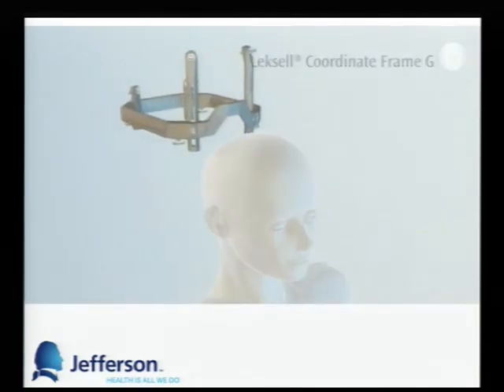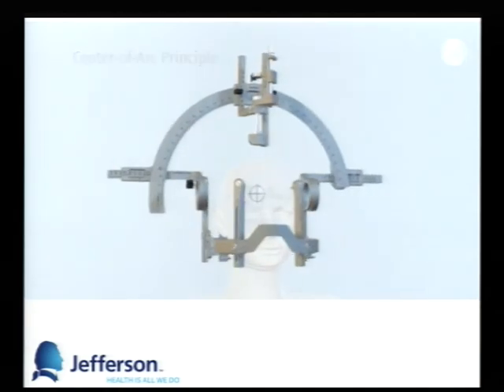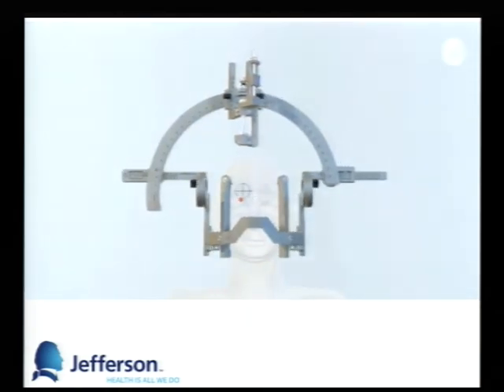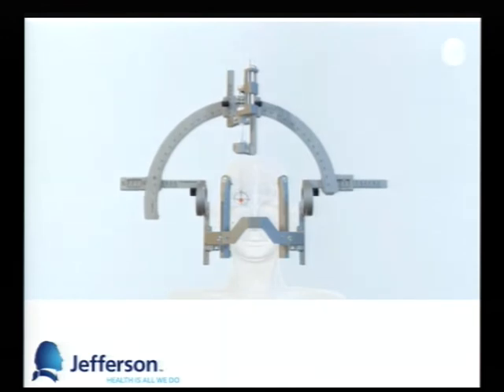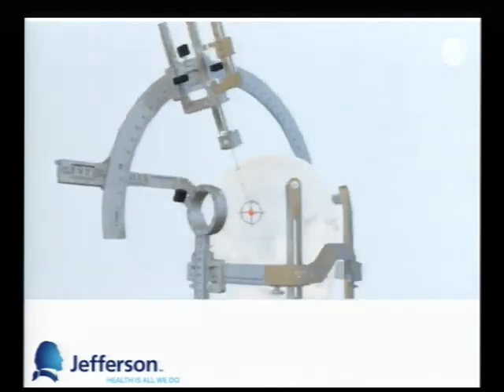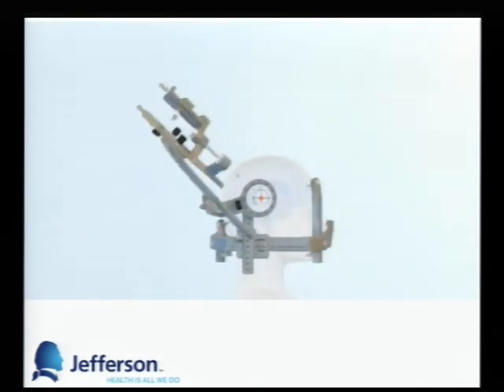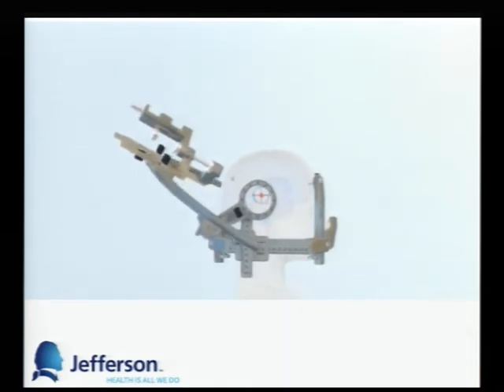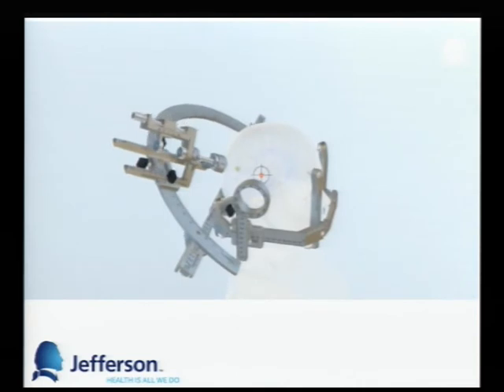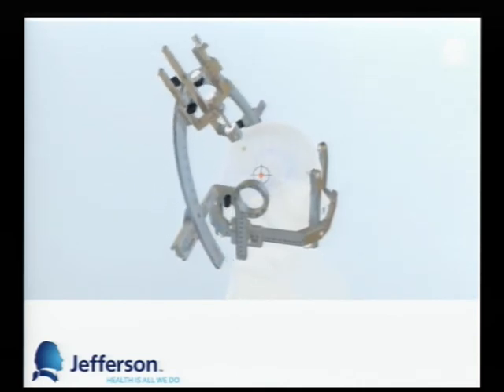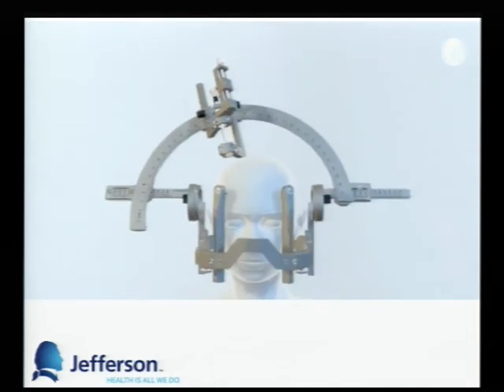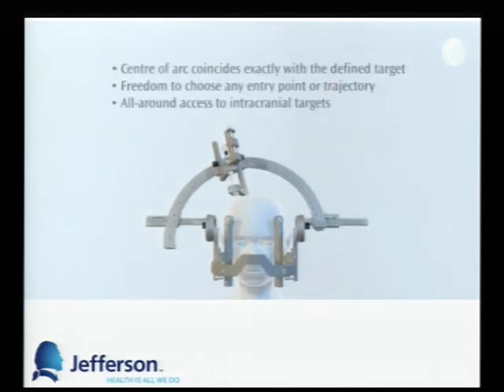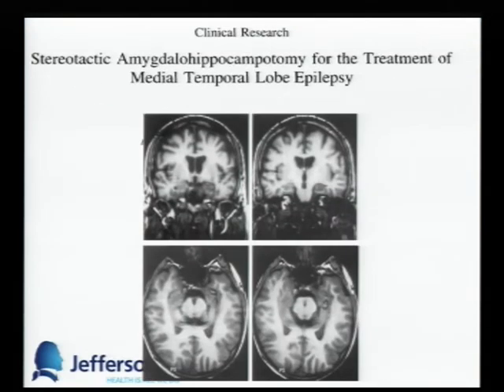And once you have the fiducial scan, you define stereotactic space. And this arc is there, and the concept of stereotaxy is that any trajectory on this arc, from any angle, which can also be manipulated at the ring or the arc, will always hit the target once the target is calculated based on fiducial space. So that is the concept of stereotaxy that was given to us 50 years ago, believe it or not, and then implemented.